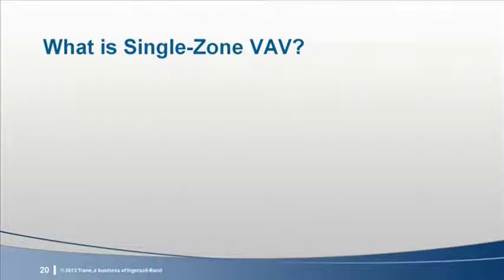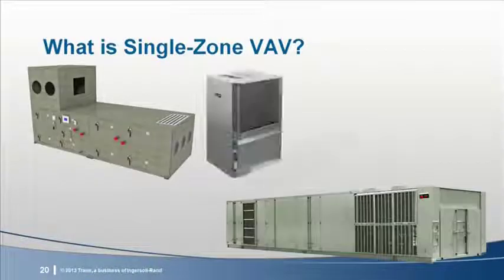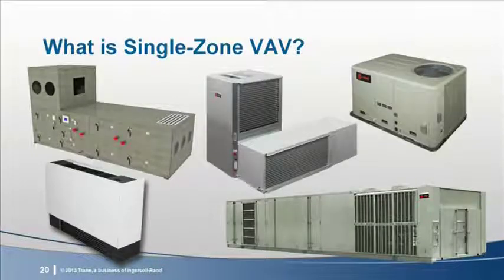Eric? Put simply, Single Zone VAV is any airside system that delivers conditioned air to a single zone with a variable volume supply fan. These may be either 2-speed fans, variable speed drives, ECM motors, or other means to adjust supply airflow when operational conditions change. Single Zone VAV systems can include fan coils, water source heat pumps, rooftop air conditioners, or even air handlers. Single Zone VAV control can really be applied to a wide range of equipment.